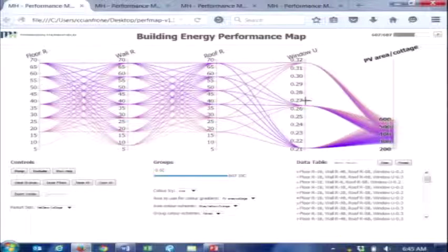And not to say that improved levels of envelope aren't important. And when you get down to whether or not you meet your design objective, you can start to say, well, okay, what if I wanted to use less PVs? PVs are expensive. Is it worth it? For every 100 square feet of PVs, I'm saving $10,000 on solar panels. What does that buy me in more insulation? Does that trade-off make sense? And you can start to make those decisions very quickly in that design setting. So kind of a unique outcome is the area of the roof is driving the performance.